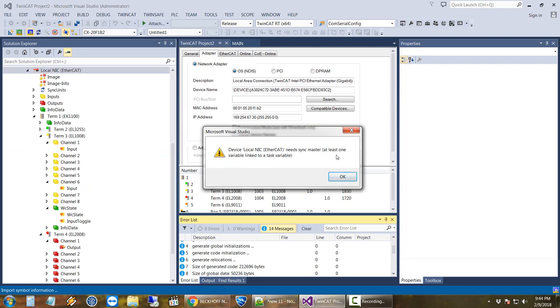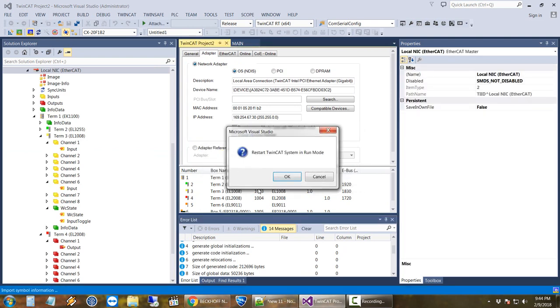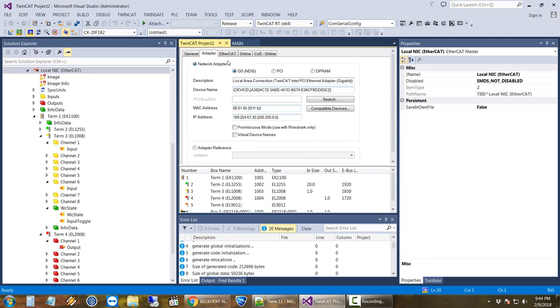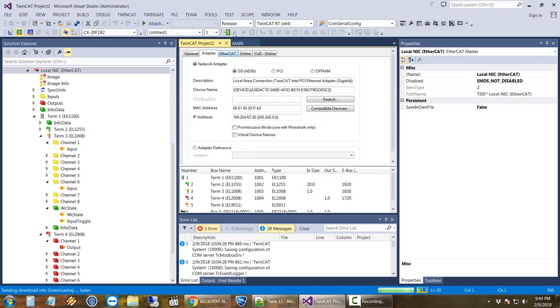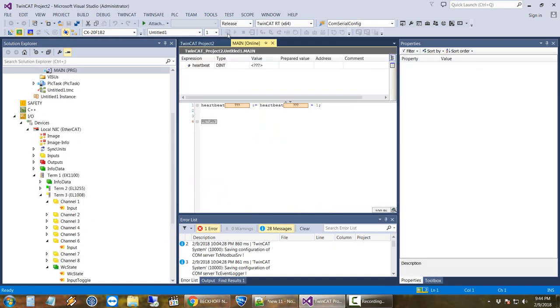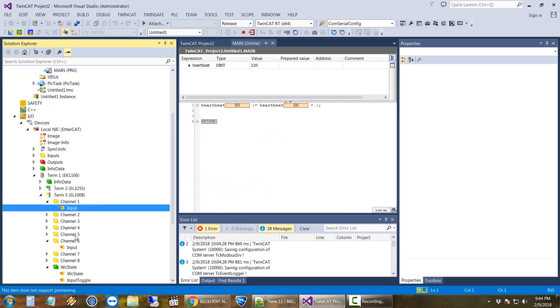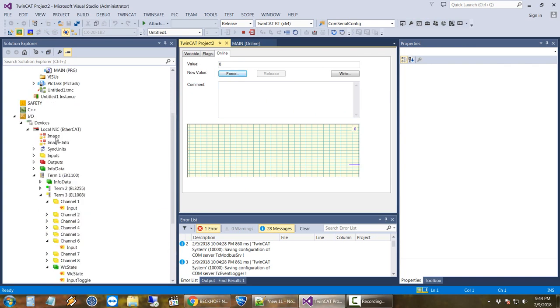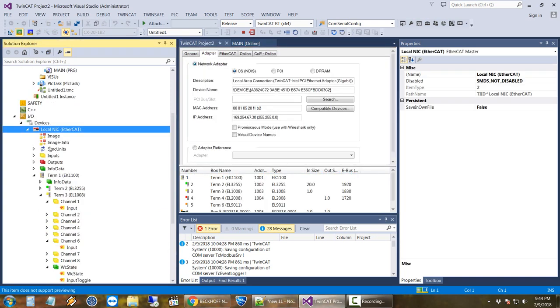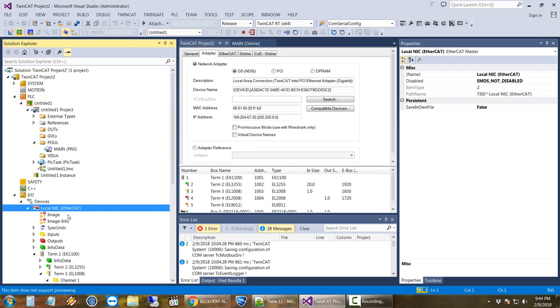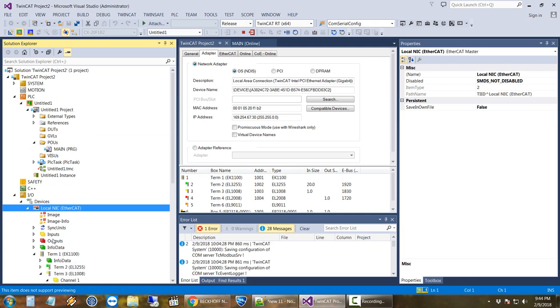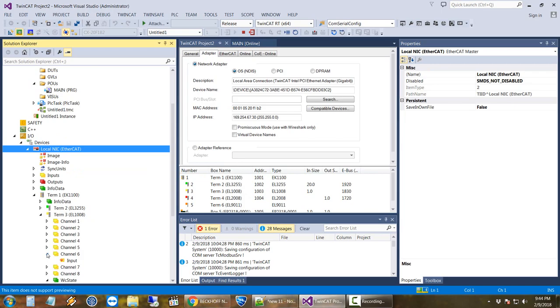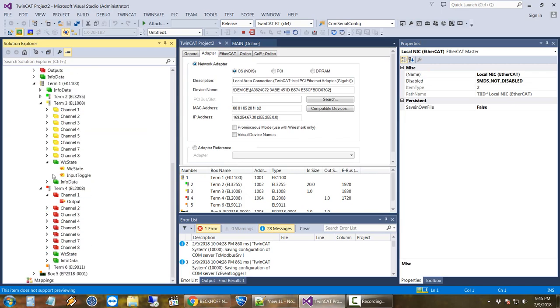Okay, so this error message, it says it needs at least one variable linked to a task variable. So the way this works basically is you've got, we talked about tasks in the first series. So I'm not going to go too much more into them. But basically, these guys are saying, hey, I don't have anything linked to me. So I don't know how fast you want me to run or anything. So these are essentially not going to do anything right now. So even if I were to go and set one of these outputs here, it's not going to actually happen on the slice. Because something on this network card needs to have a sync master. So you can either do that by making a fake task or by linking up one of these guys here. That will do it if you're just playing around right off the bat. But since we have real I.O. we're going to mess with, we'll just go ahead and start that process next.